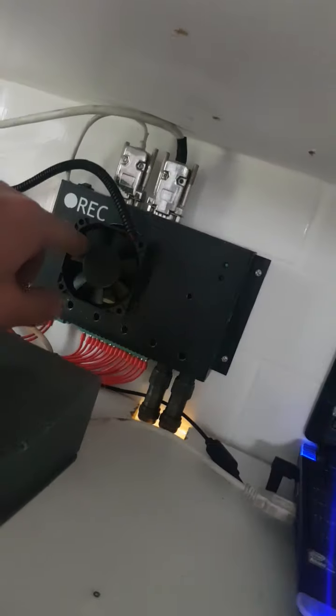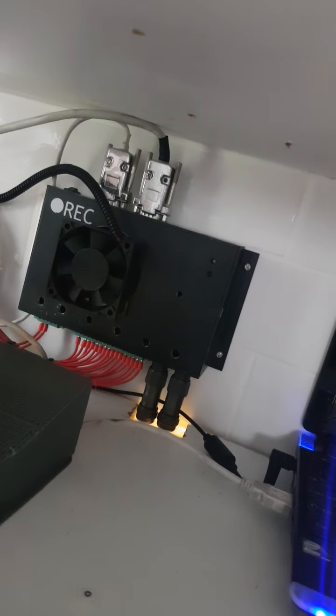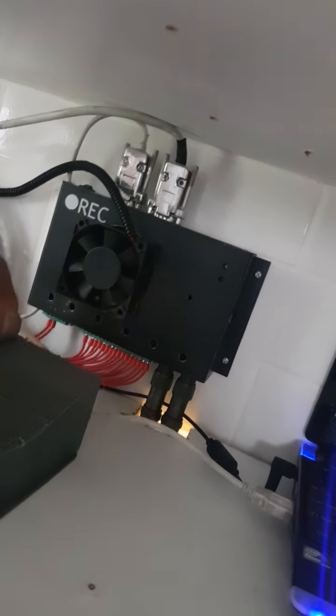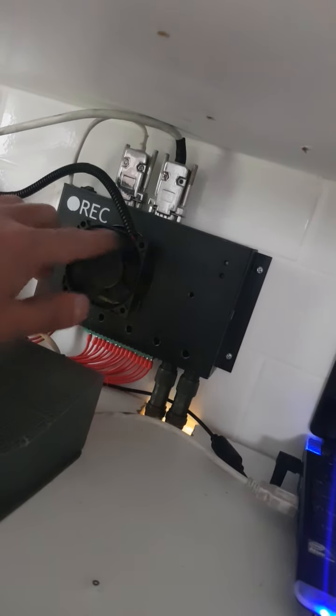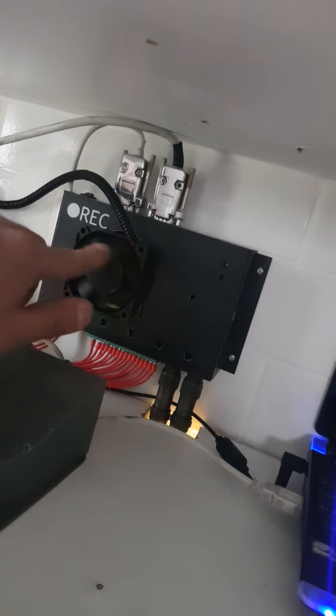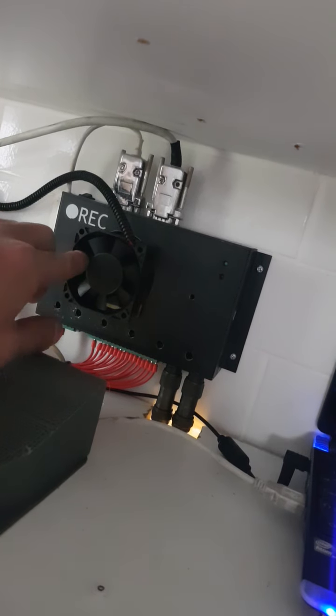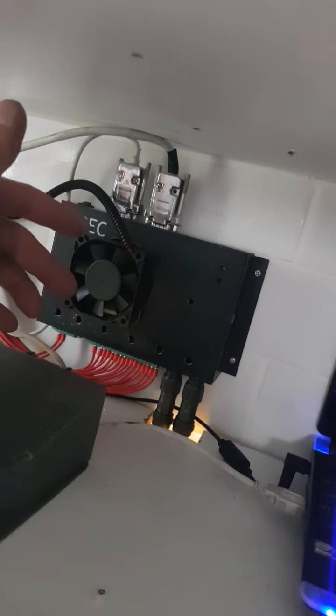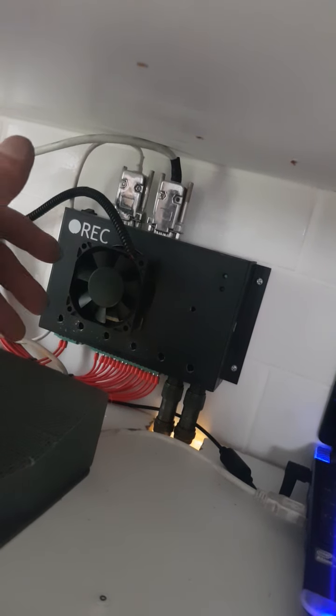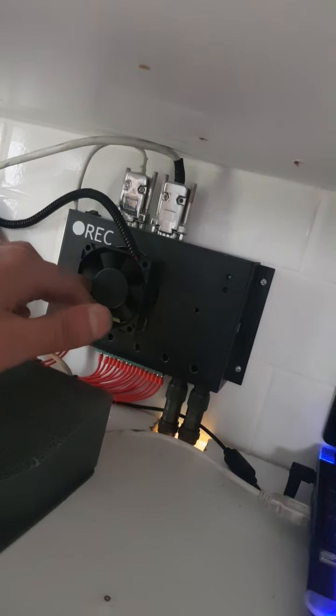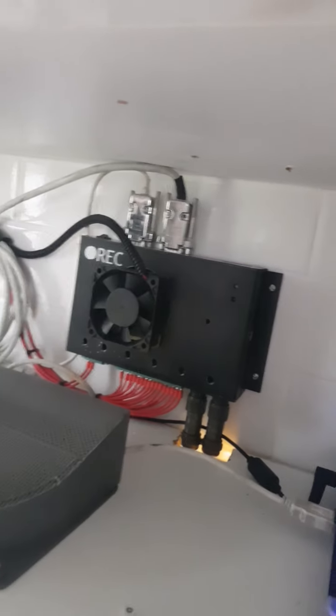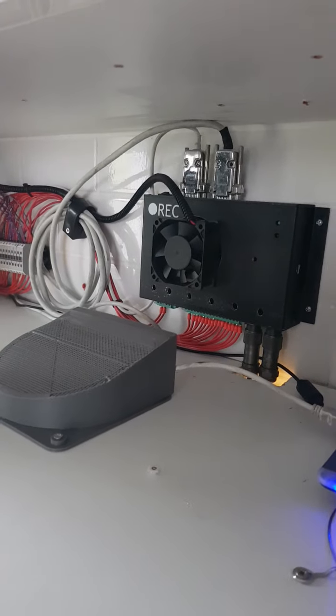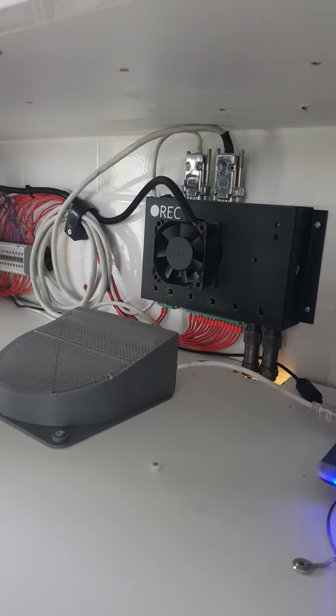We've tried all different ways, tried heat sinks and this, that, and the other - it just gets too hot when trying to balance. It's as simple as that. And then it will trip out because it will say that the BMS is too hot. It won't trip the system, but it will stop it from balancing. So the fan there will just cool it just enough to keep doing what it's doing without damaging anything.